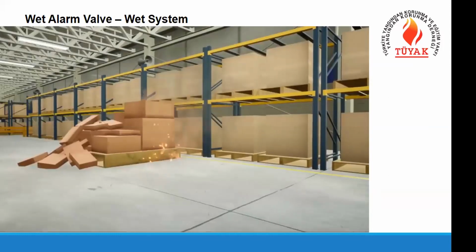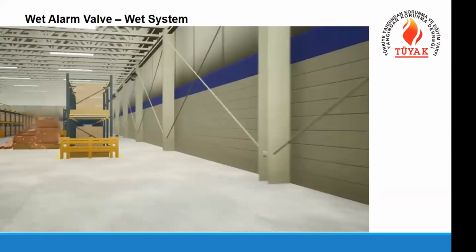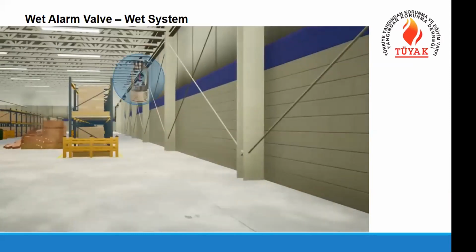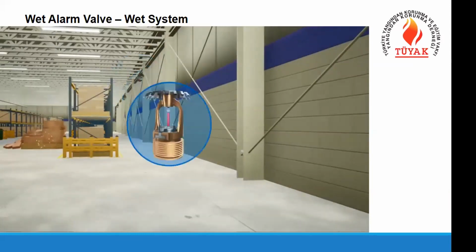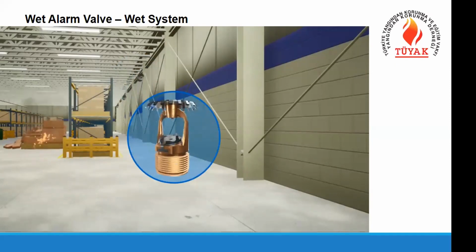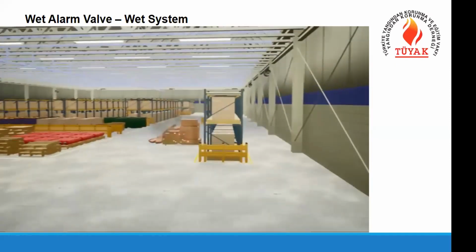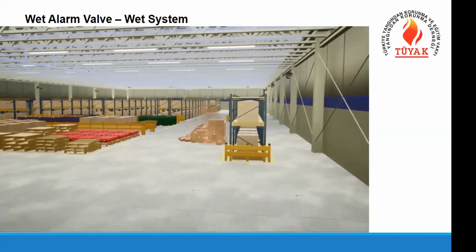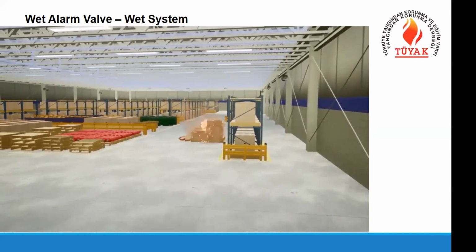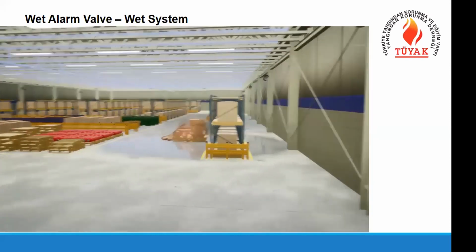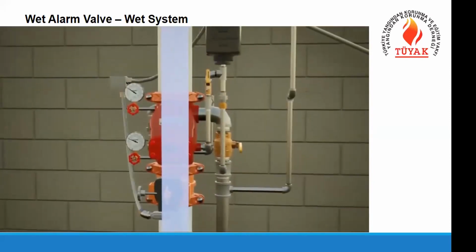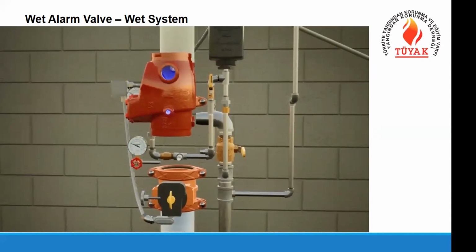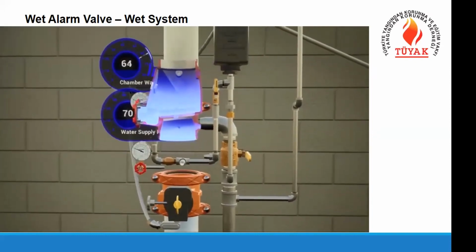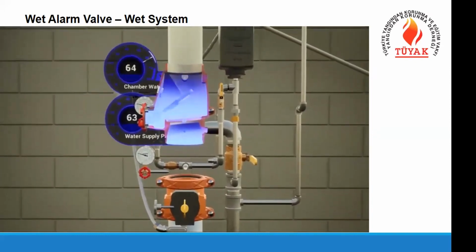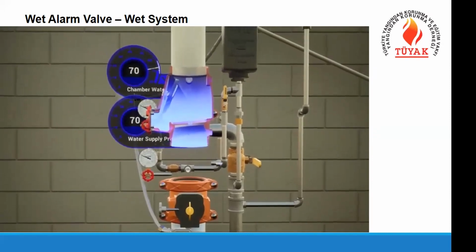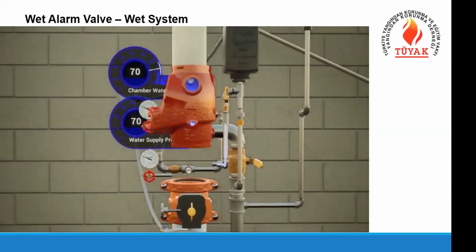A fire has started in the building. As the fire grows and the heat reaches the rated temperature, the sprinkler will activate. Since this is a wet system, water is already in the pipes, allowing the immediate delivery of water to the fire. After the sprinkler activates and water flow is established, the clapper is fully lifted off of the seat and the alarm ports are exposed, allowing water to enter and fill the alarm line.